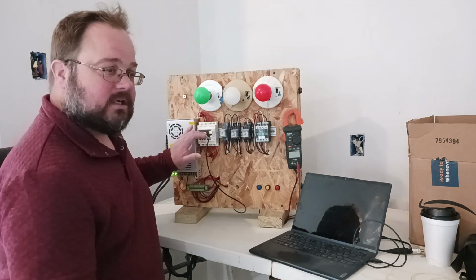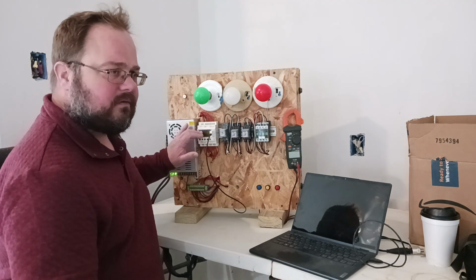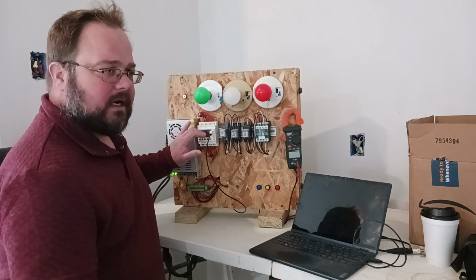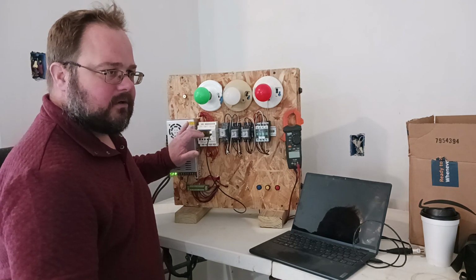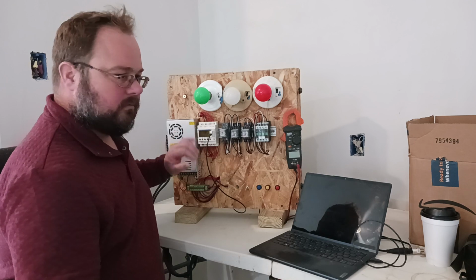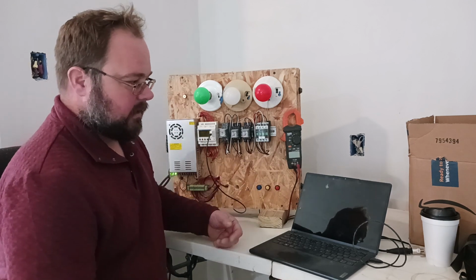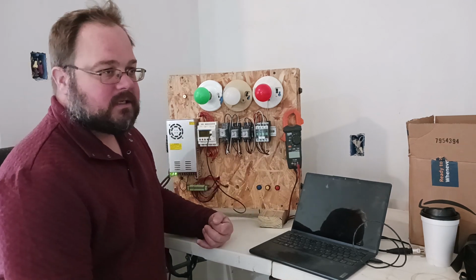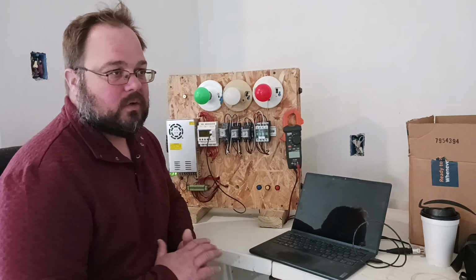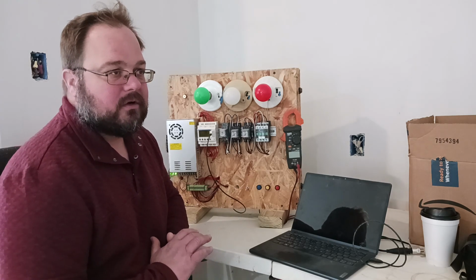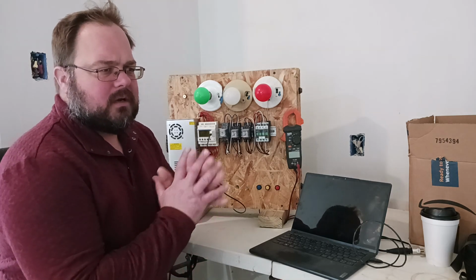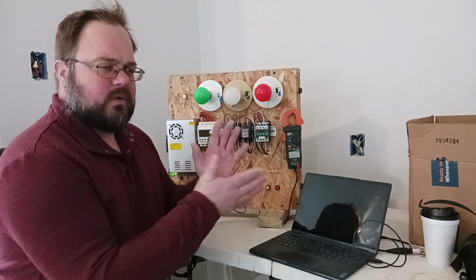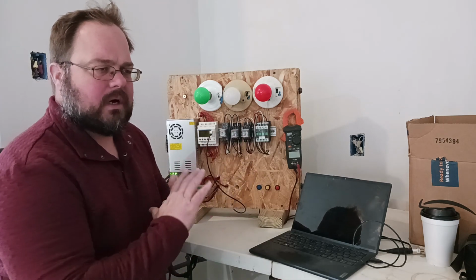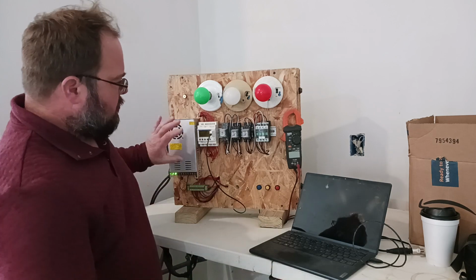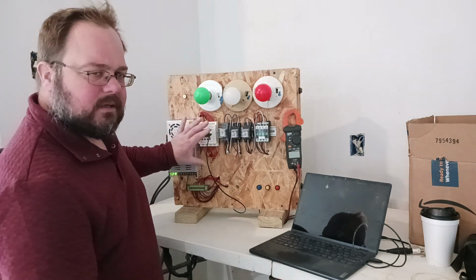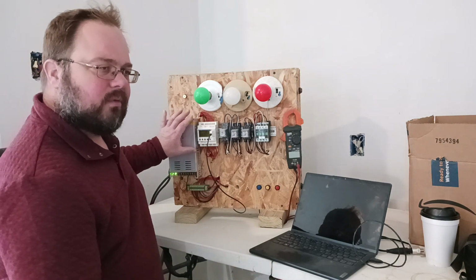These Schneider Zelio Logic PLCs are pretty affordable and pretty good for trainers, to train yourself. The Zelio Logic PLCs I've seen in my program vary - some need 12 volts, some need 24 volts, some need 120 or 240 volts. So there are a lot of PLCs, both in the real world and in my program, with different requirements. If you get a PLC, know that your power supply needs to match the requirements, not only in voltage, but wattage.